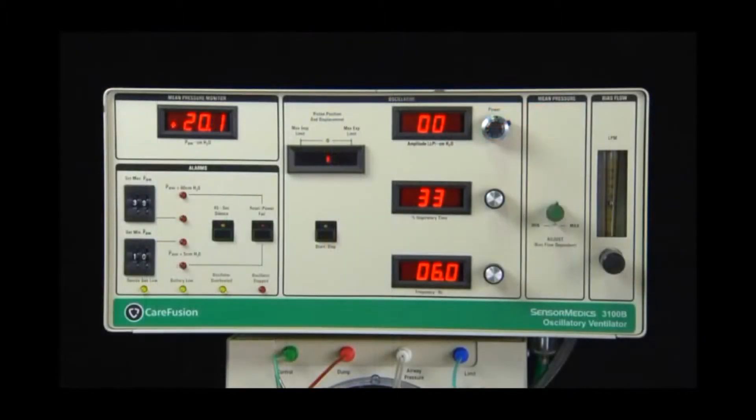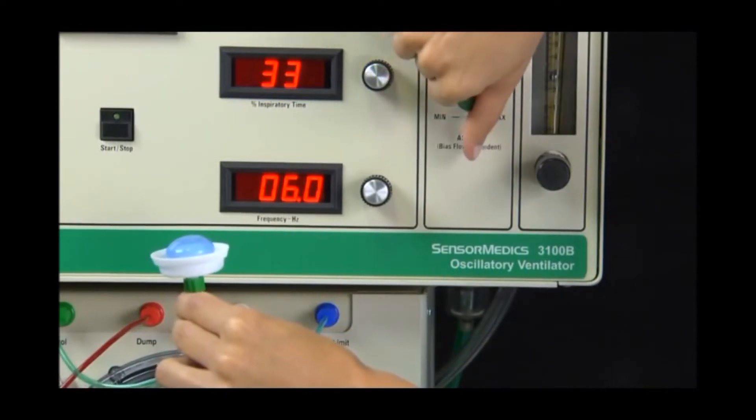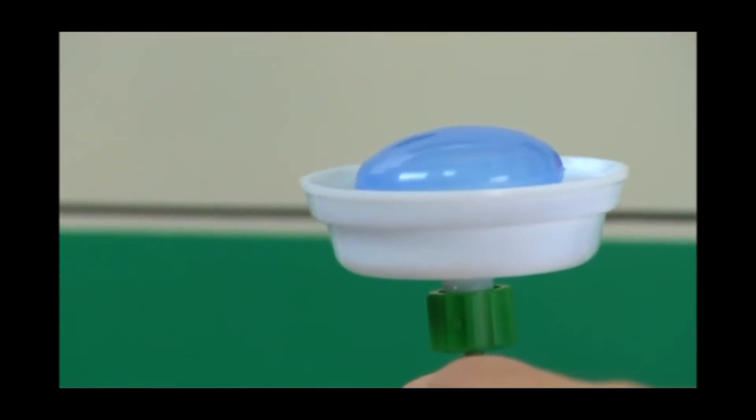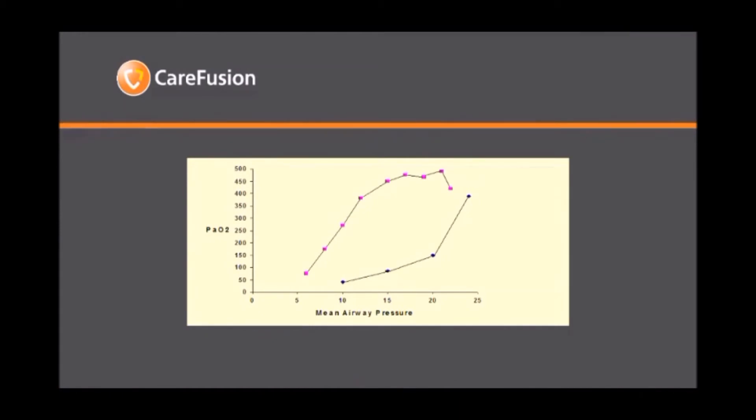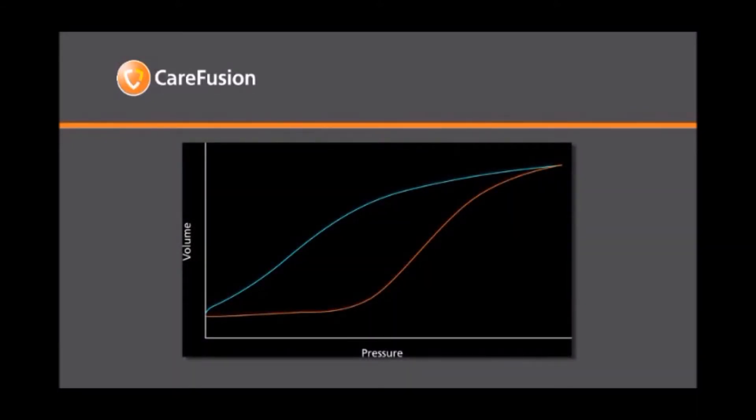The knob on the front of the instrument labeled adjust controls the mean airway pressure. Manipulation of this control changes the inflation of the balloon valve on the expiratory limb of the circuit. This results in changes to the mean airway pressure. Mean airway pressure is utilized to establish lung volume and thereby directly affects oxygenation. High frequency oscillatory ventilation strategies often refer to the decoupling of ventilation and oxygenation. These strategies are based on the assumption that the first priority is given to establishing adequate lung recruitment.